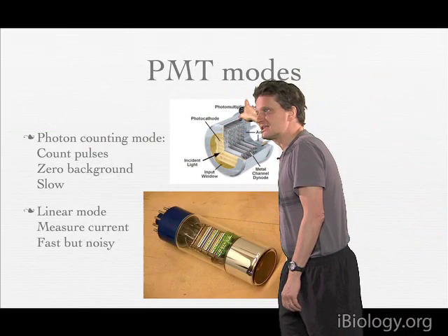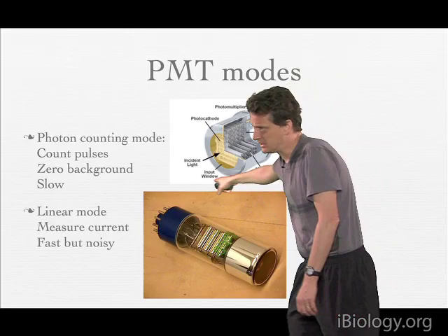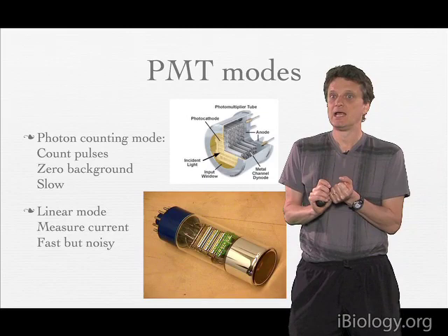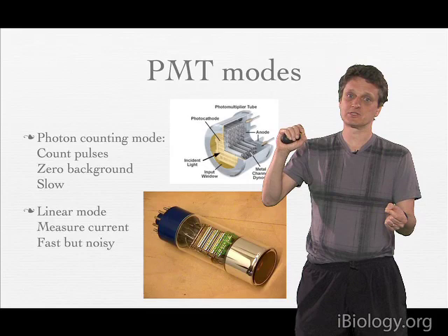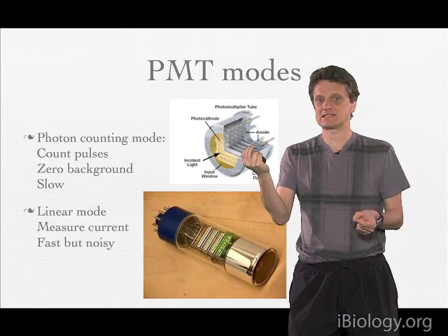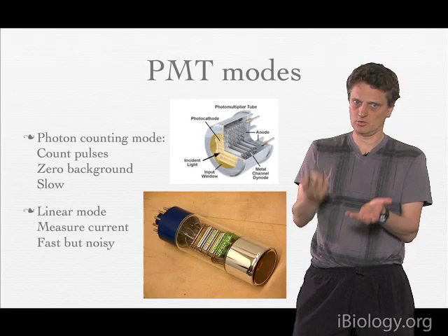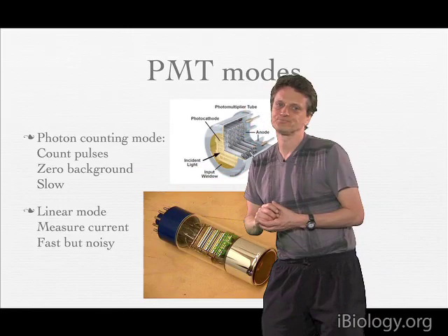There are other types of designs for PMTs, but they all work on the same principle using dynodes. Here you see a real example of what such a tube looks like. You can run them in different modes. One mode is the photon counting mode, where you set a very high gain so that every photon that comes in and is converted into an electron is counted as a single pulse. The advantage is that you have no background, because either you have a hit or you don't. The downside is that this is very, very slow.